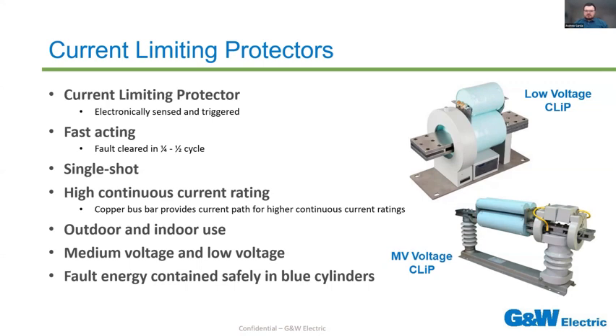What really makes CLIP unique relative to other options, what makes it really competitive, is its high continuous current rating. The ratings that CLIP can go up to, in endurance of current limit, can really only be matched by reactors. Think up to 4,000 or 5,000 amps continuous, depending on that voltage rating. By default, they are also both outdoor and indoor rated, meaning that you can install these outdoors without an enclosure behind a fence or pole mounts just by default right off the shelf. They can be installed in an enclosure, both outdoors and indoors as well, with no issue.